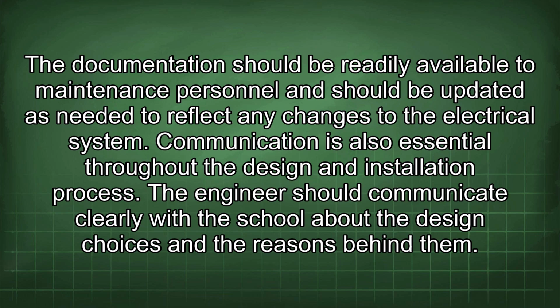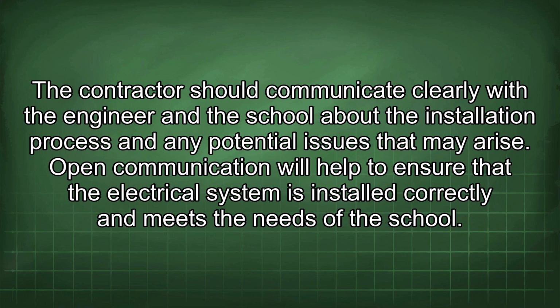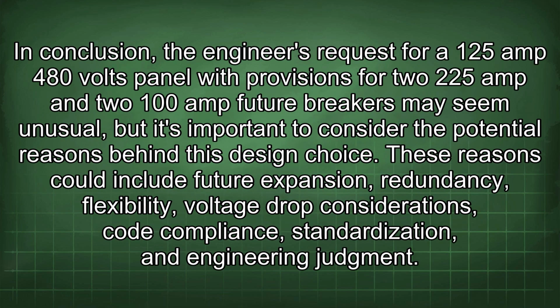The engineer should communicate clearly with the school about the design choices and the reasons behind them. The contractor should communicate clearly with the engineer and the school about the installation process and any potential issues that may arise. Open communication will help to ensure that the electrical system is installed correctly and meets the needs of the school. In conclusion, the engineer's request for a 125 amp 480 volts panel with provisions for two 225 amp and two 100 amp future breakers may seem unusual, but it's important to consider the potential reasons behind this design choice. These reasons could include future expansion, redundancy, flexibility, voltage drop considerations, code compliance, standardization, and engineering judgment.